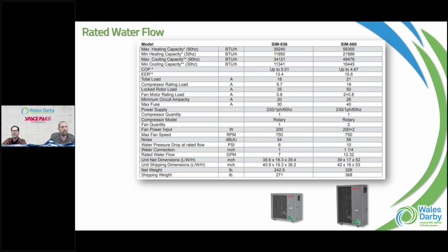So looking here, we're just looking at the specs on the two systems in that SIM model, the 36 3-ton and the 5-ton. Obviously we just talked about the electrical capacity. What we look for now is the size of pipes, to push the BTUs back into that buffer tank and vice versa. We do have a rated water flow that has to go through the machine. When we size that circulator, for the SIM 36 that's going to be 7 GPM and just over 12 GPM for the 5-ton. That could change now with glycol in the mix.